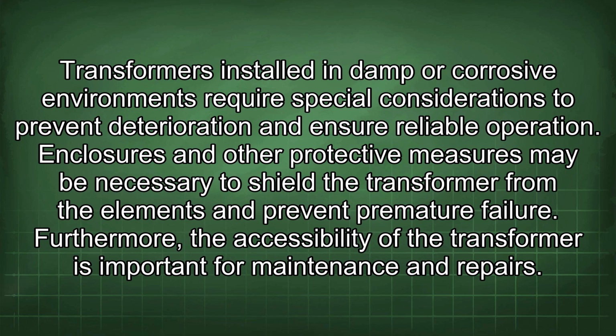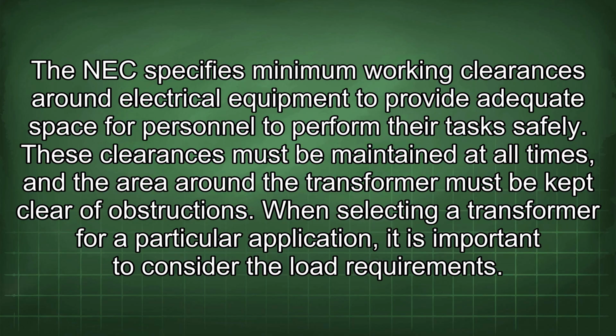Furthermore, the accessibility of the transformer is important for maintenance and repairs. The NEC specifies minimum working clearances around electrical equipment to provide adequate space for personnel to perform their tasks safely. These clearances must be maintained at all times, and the area around the transformer must be kept clear of obstructions.